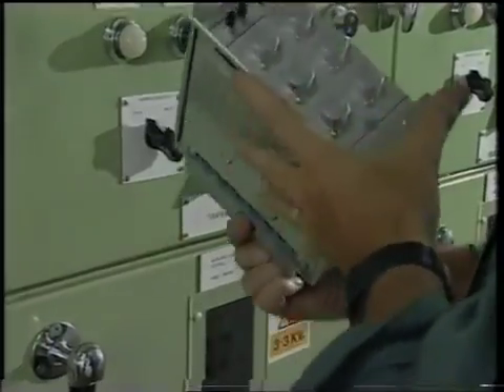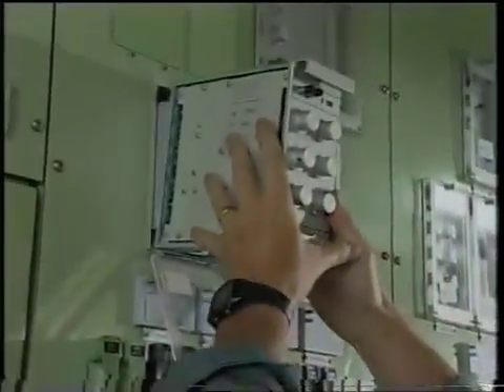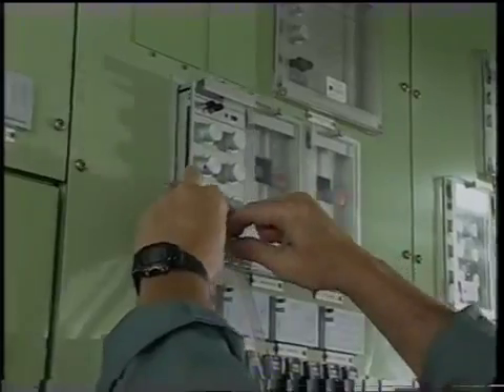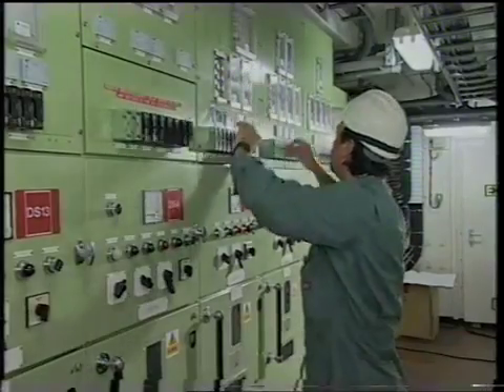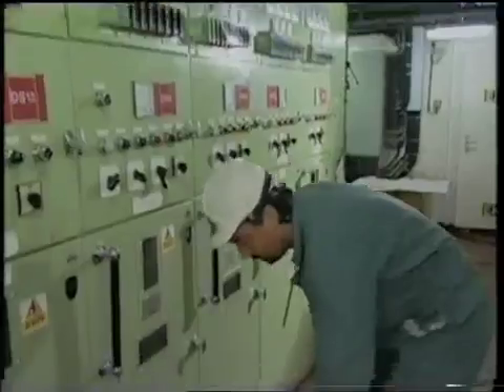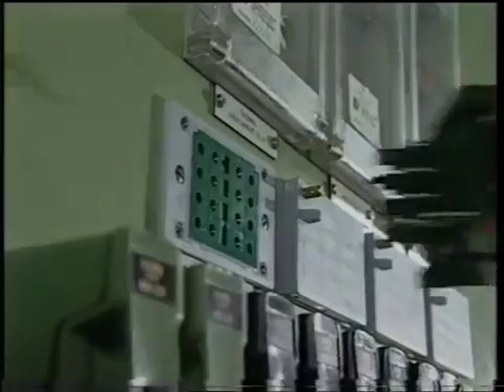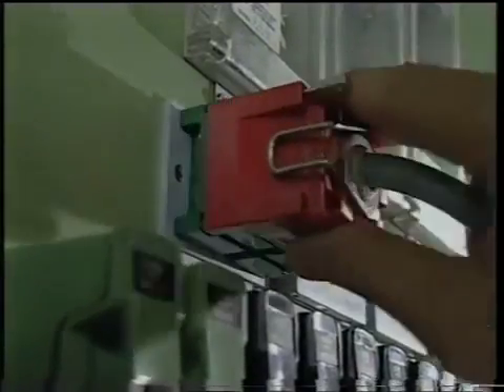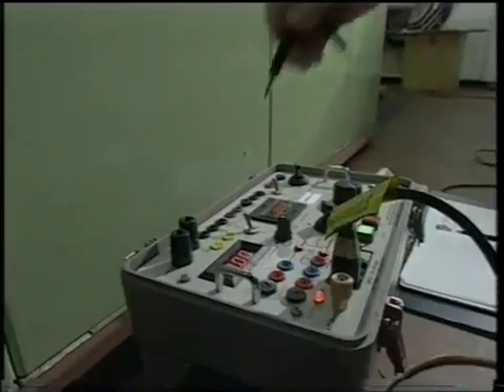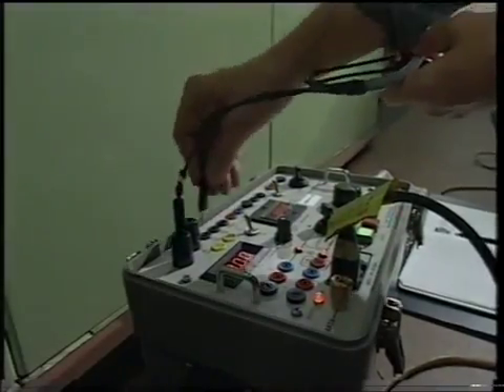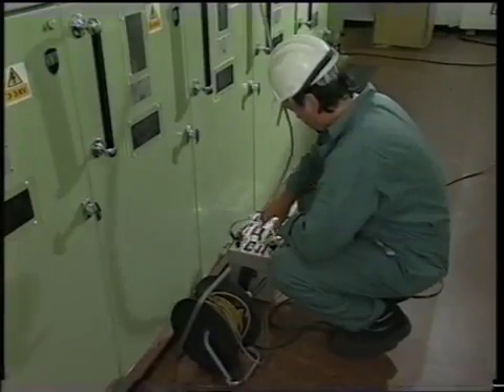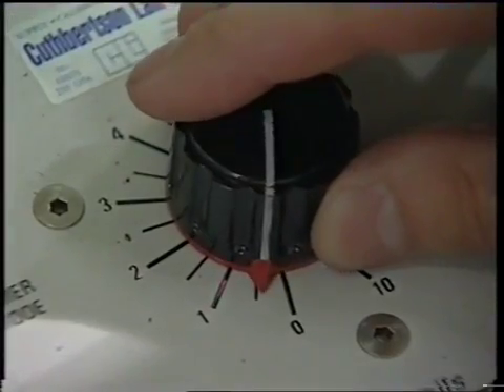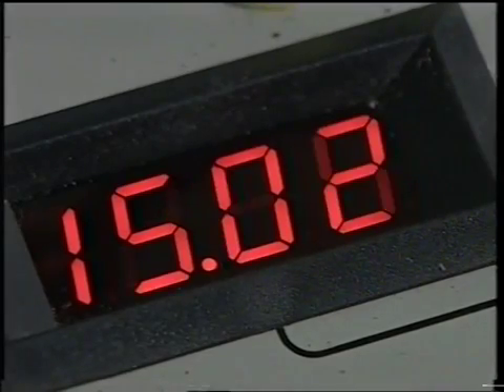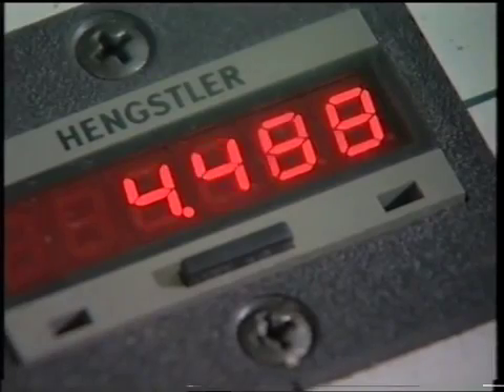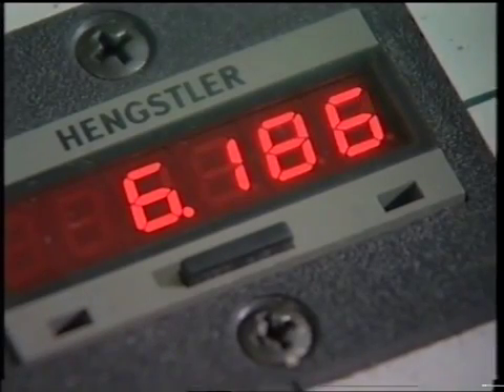Electrical circuit equipment requires special protection relays, which are usually fitted on the front panels of main and sub-switchboards. Periodic maintenance testing of such relays is necessary to confirm their operation and accuracy. This work requires calibrated test equipment and is usually done by outside contractors during a major refit in dry dock. The equipment injects a set current and records the time for the relay to trip.